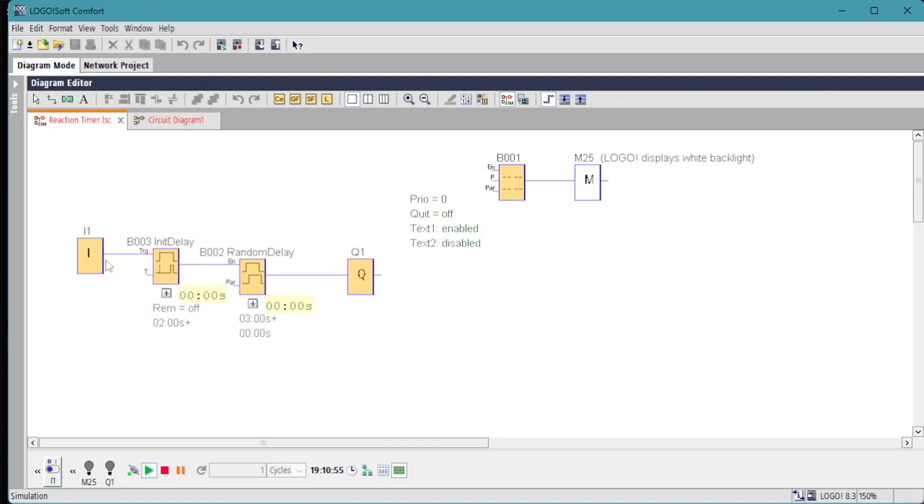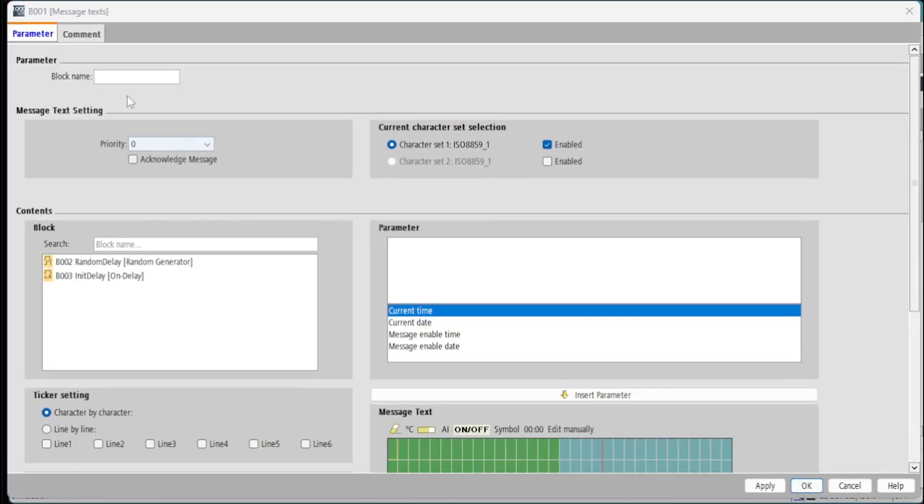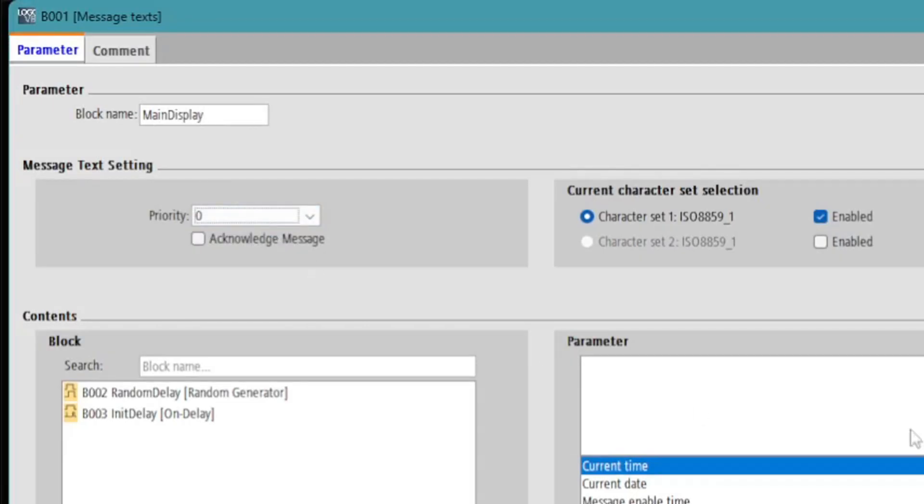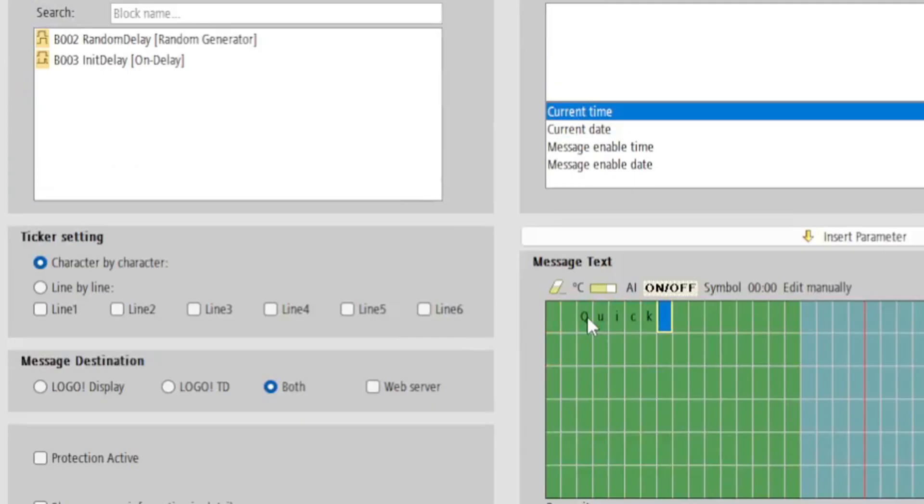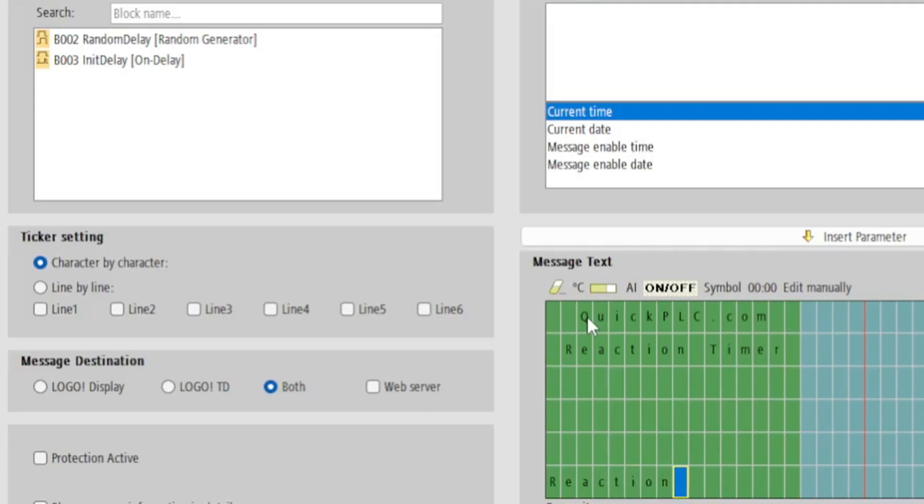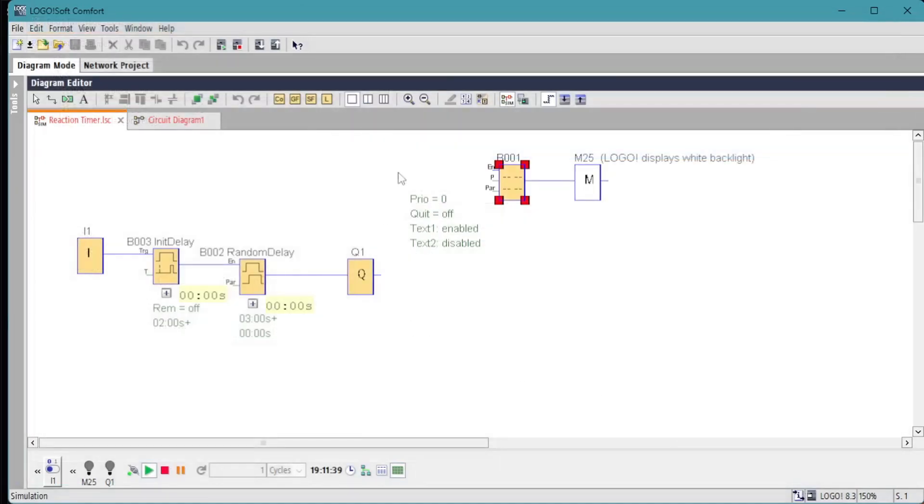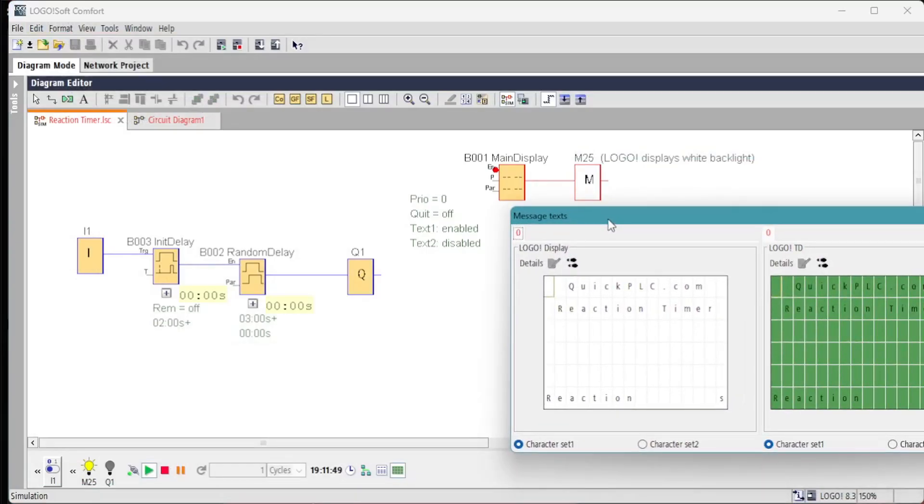We'll configure our message display text. Note that this defaults to priority zero, so this is the lowest priority message. Any subsequent message texts we add will have a higher priority number and be visible on top of this. See the message text function video for more details on this. We want the message display to be on all the time, so we'll set the enable input to be high by default by using an invert connector on it.